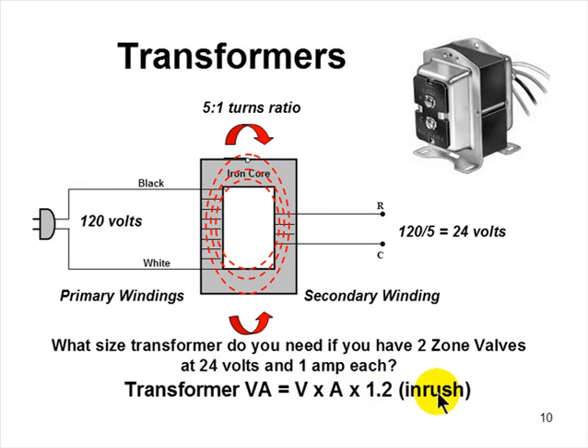That's 20%. Inrush is low voltage locked rotor current. When you have a compressor motor that draws 20 amps, except when it starts up, it draws 80 to 100 amps, 4 to 5 times the running amps. That's locked rotor current, because you're taking that big, powerful motor from a dead stop, locked rotor, to speed. And to do that, you're going to have a heck of an increase in current, or VA. That results in a very high current draw, 4 to 5 times the running load. So your 20 amp motor is going to draw 80 to 100 amps for a few seconds while it gets up to speed.